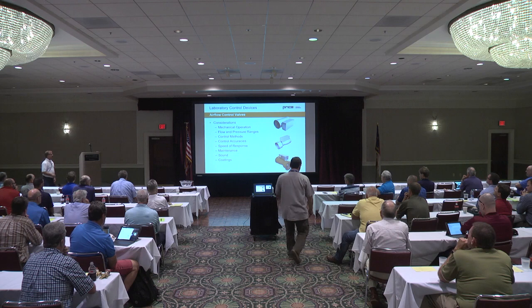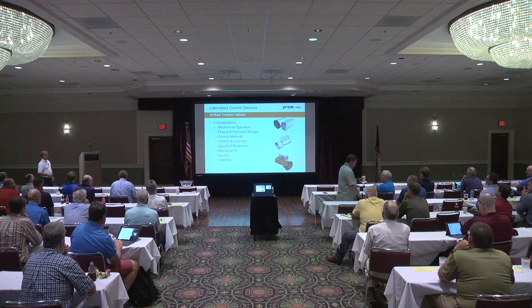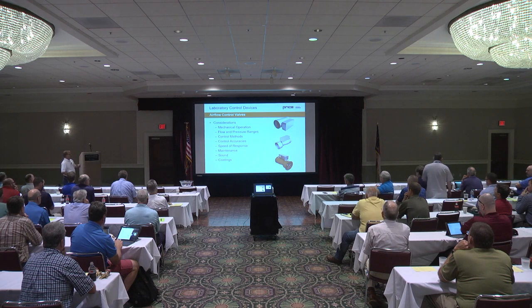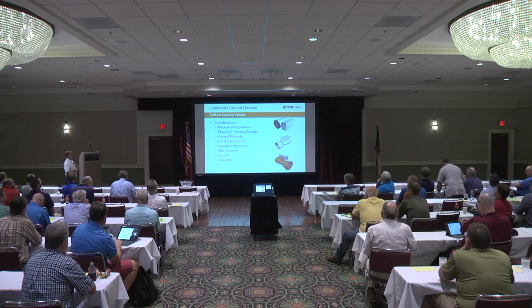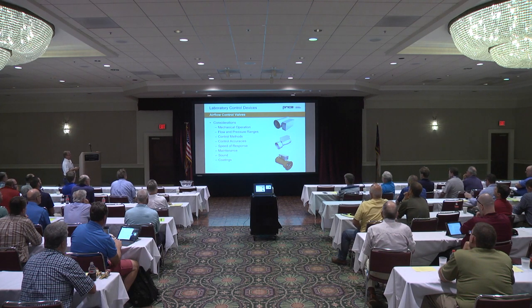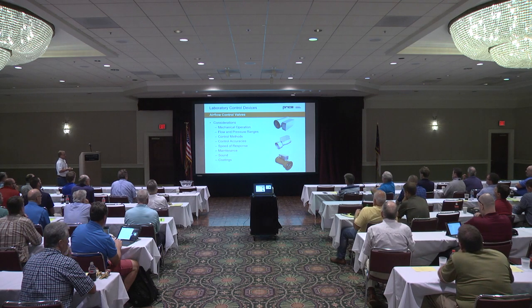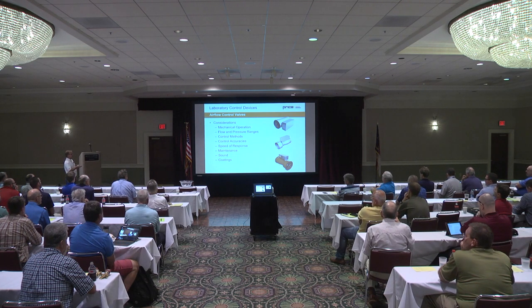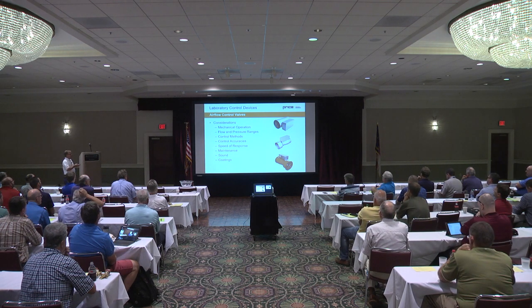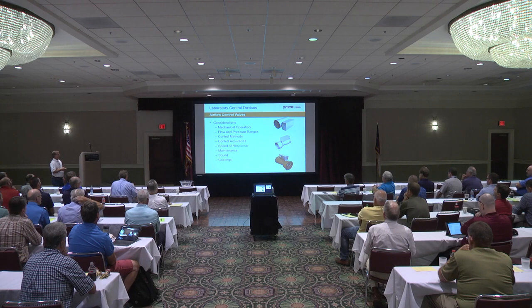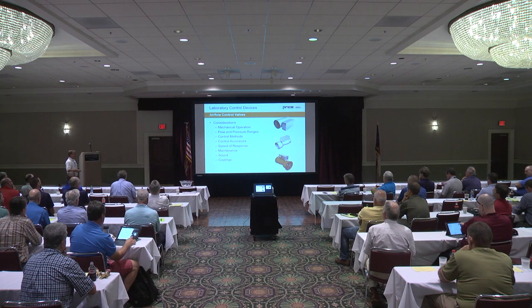So to start with, your different laboratory airflow controls, or just control devices in general. On the top is a regular terminal box with the cross flow sensors. In the middle is a Venturi valve with airflow measurement, and in the bottom is your Venturi air valve, mechanically pressure independent cone with no airflow measurement, position control. When you're talking about airflow control devices, you're looking at mechanical operation, your flow and pressure ranges, control methods, your control accuracy, speed of response, which become critical in laboratories, your maintenance, sound, and coatings for different applications such as your fume hoods.